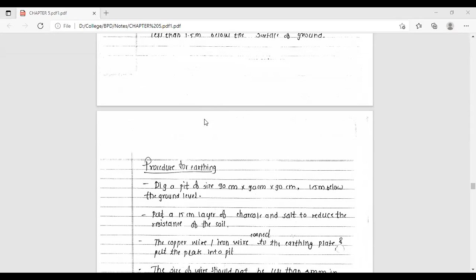Okay, and then firstly you have to prepare a layer using charcoal and salt of 15 centimeter to reduce the resistance of the soil. The copper wire or iron wire is connected to the earthing plate and the plate is put into the pit. Just we have to put that plate into the pit by connecting the copper wire or iron wire. The size of wire should not be less than 5 mm in case of copper wire, and in case of iron wire it should be 6 mm.